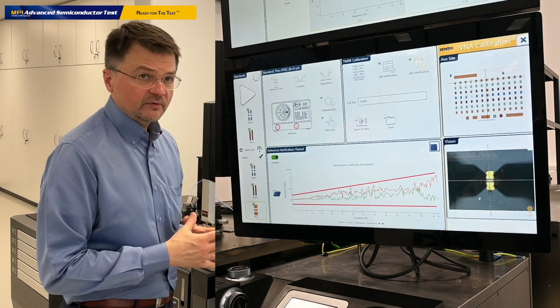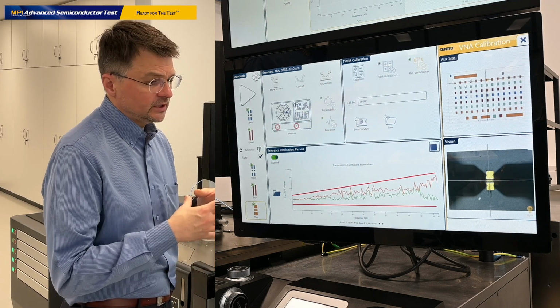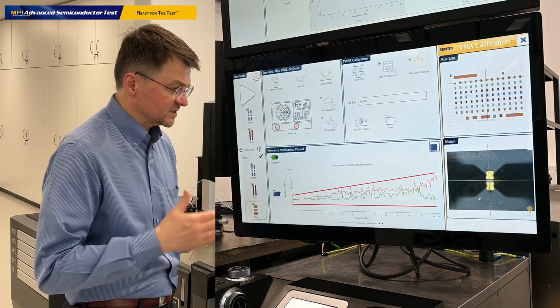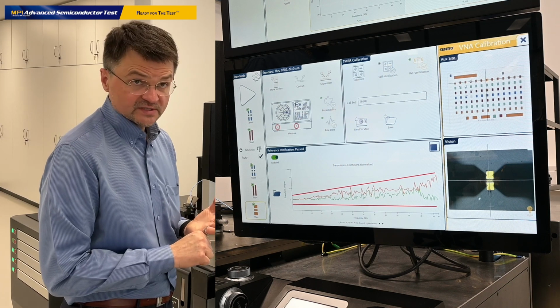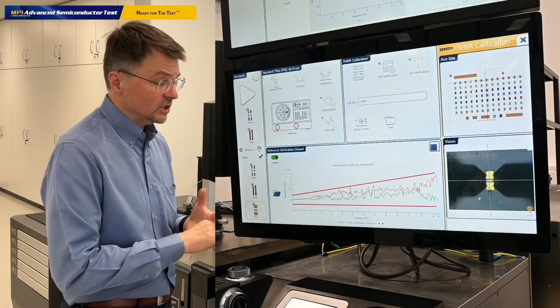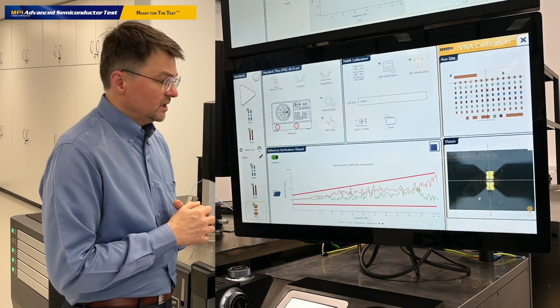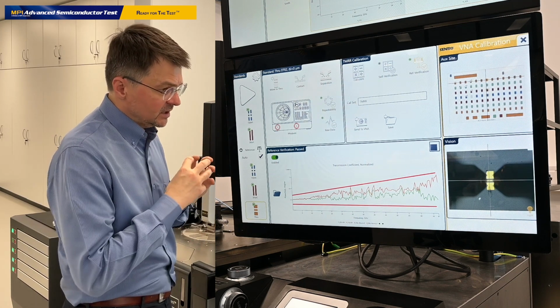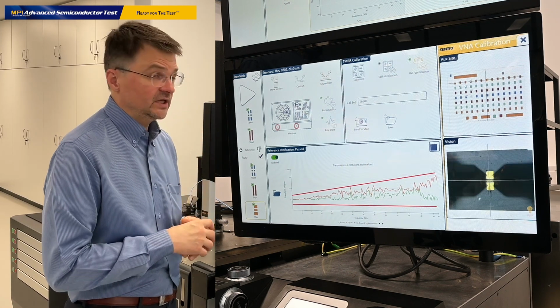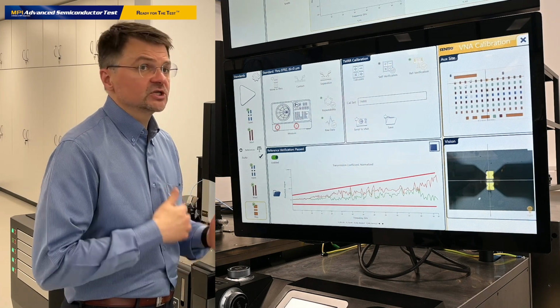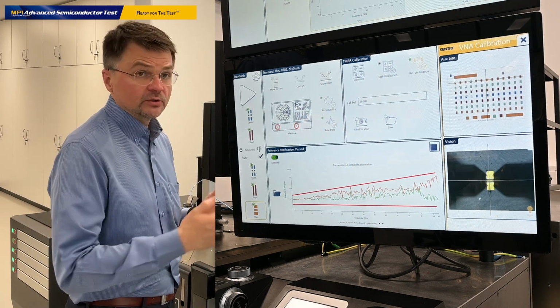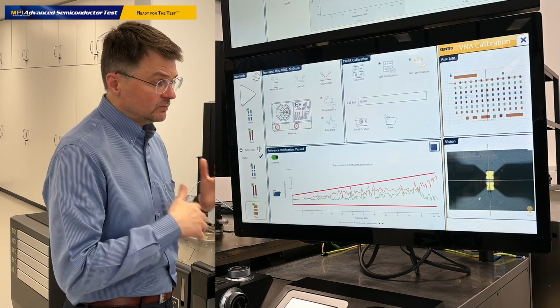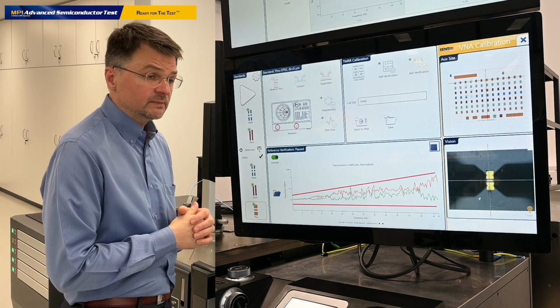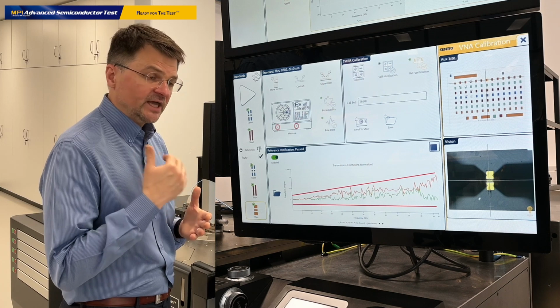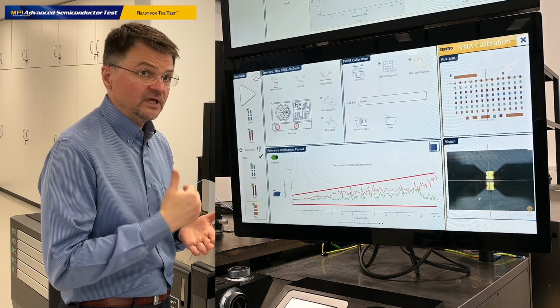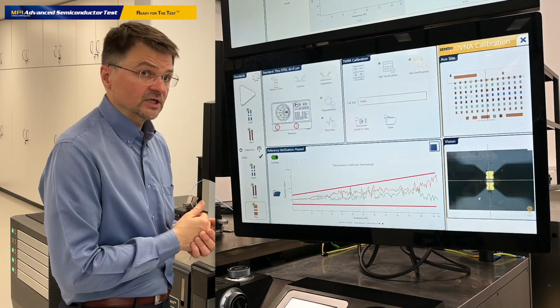By using this type of calibration verification, we usually check the following parameters: the stability of our setup, drift of our internal setup, and also contact repeatability. If you want to qualify and make a full quantitative verification of the calibration accuracy, we must measure some specific elements, such as a long transmission line, for instance, whose models are also available from the Calibria database. Based on these results, we will have a full understanding and qualification of the accuracy of the executed calibration process.